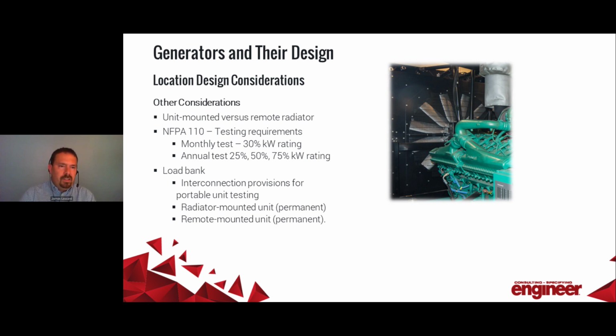code NFPA 110 dictates a monthly test, a 30% kW rating of the generator. You're not always able to accomplish that. Maybe the actual building load doesn't reach that threshold. And so, maybe you bring in a portable load bank. Dana touched on that, the need to provide provisions to be able to tie in a temporary load bank.